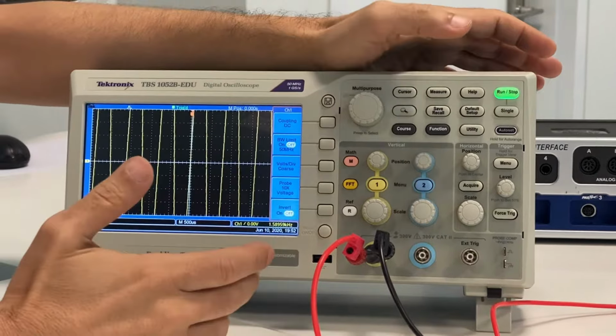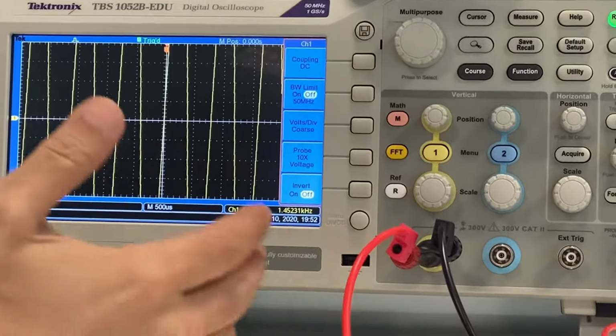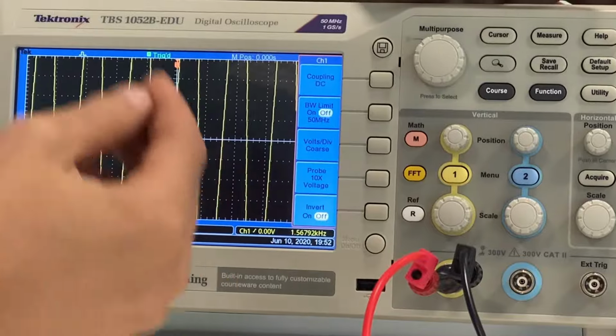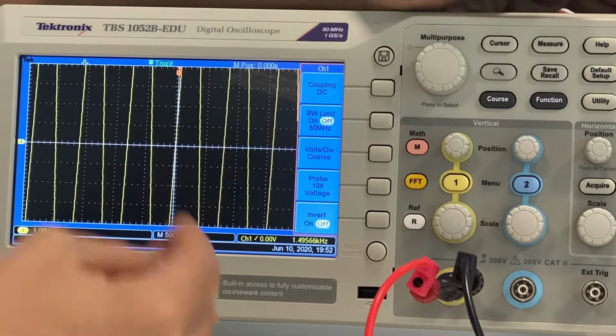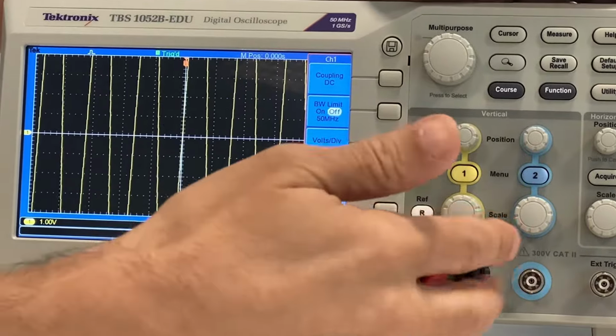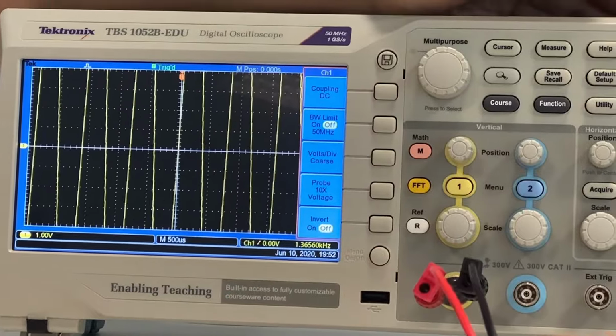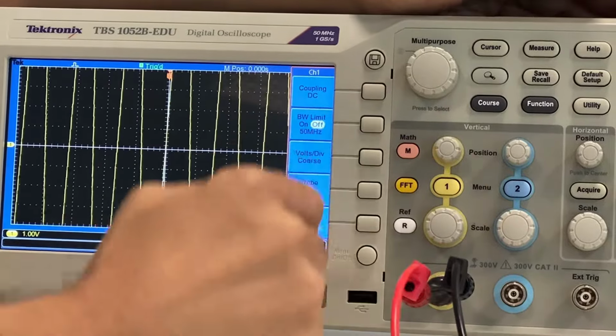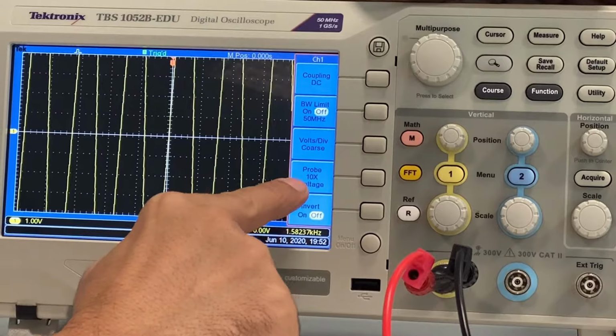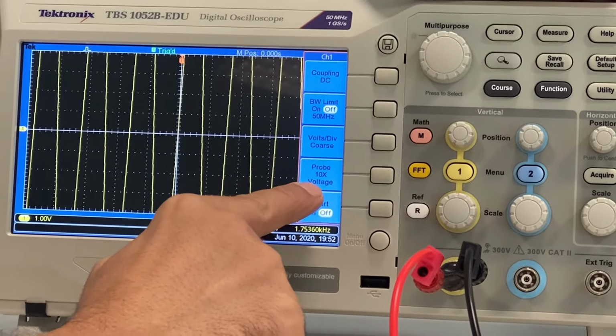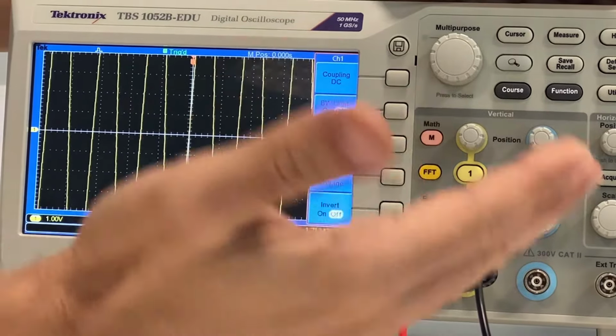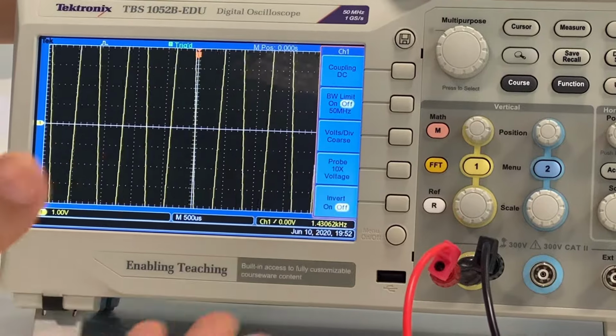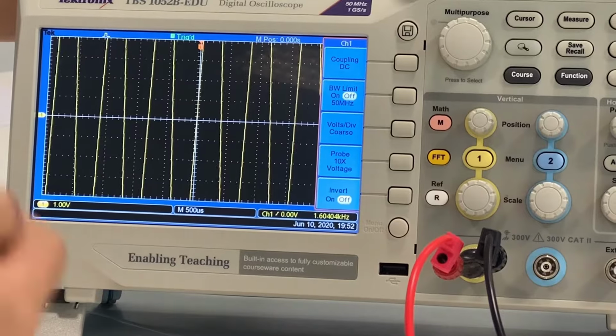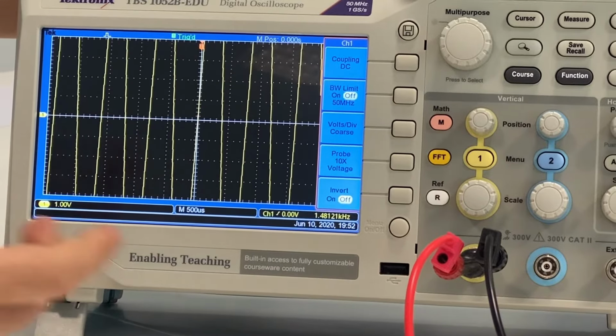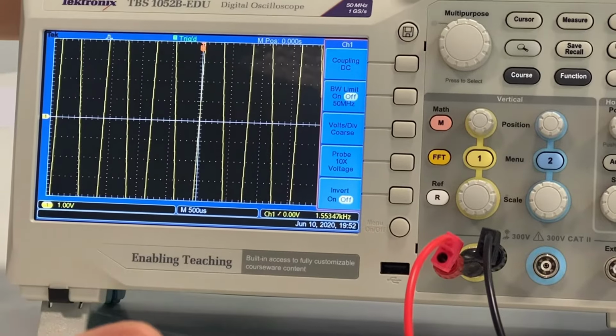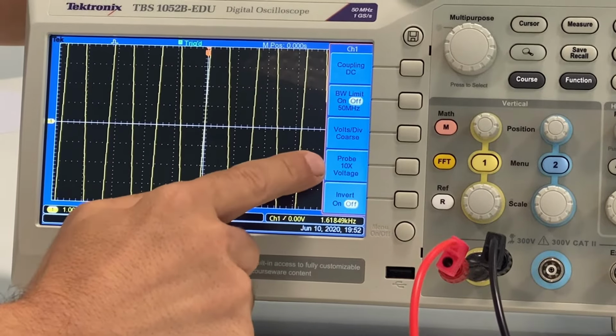Now, when you press the default setup, the oscilloscope assumes that you are going to use the probe that comes with it. But we are not going to use the probe. We are using the banana plug wires directly, okay? So if you look here, it says probe 10x voltage, which means that the oscilloscope assumes that the voltage that it is reading is attenuated 10 times or reduced 10 times. So it's going to give you a value multiplied by 10. So we have to change this first.